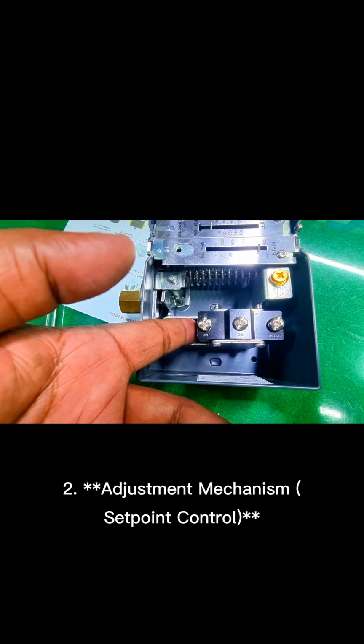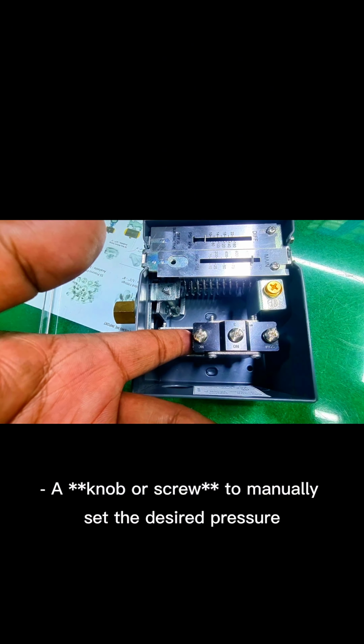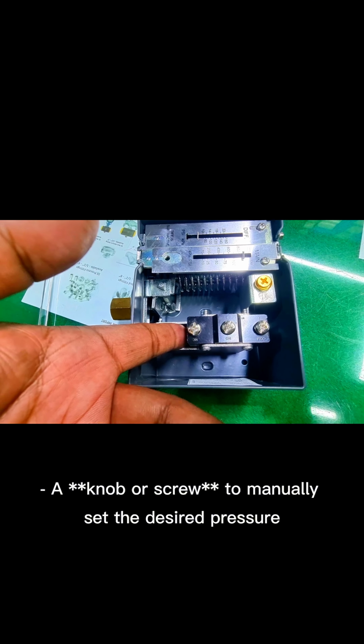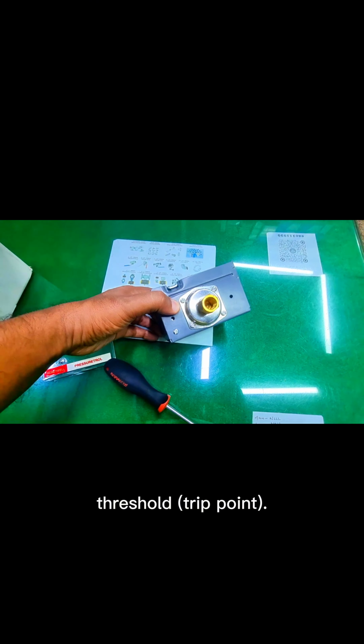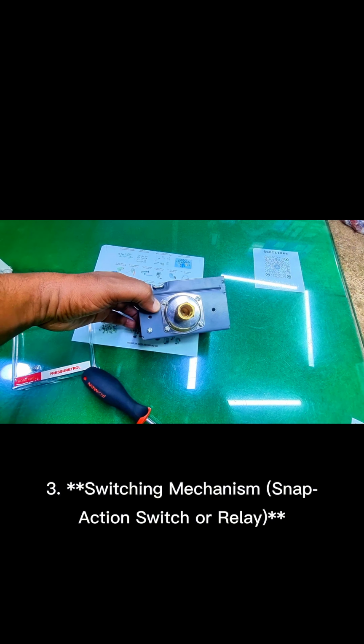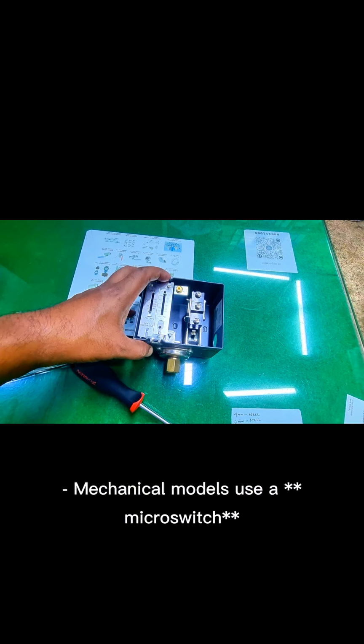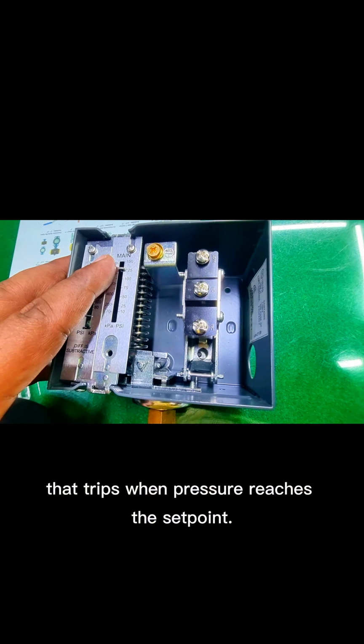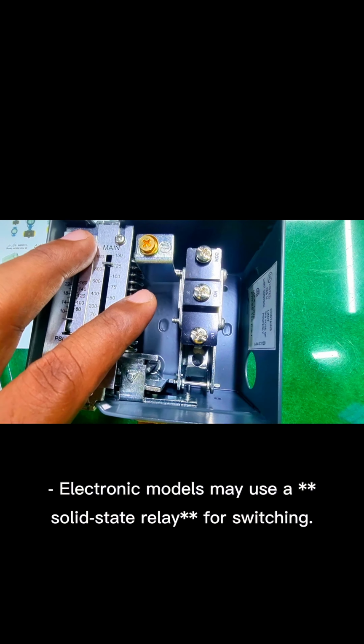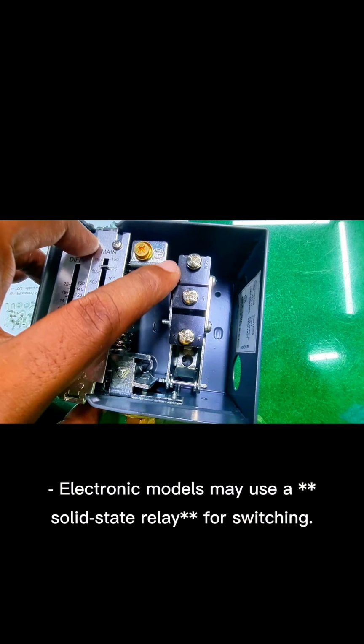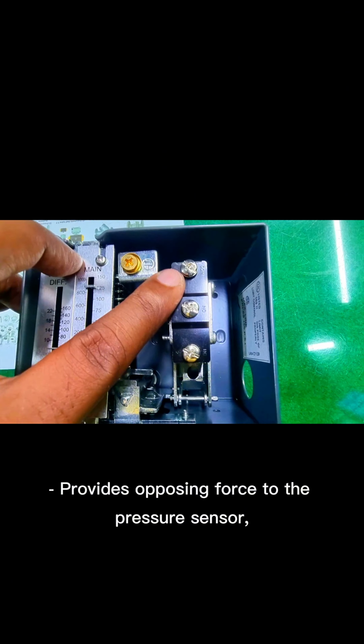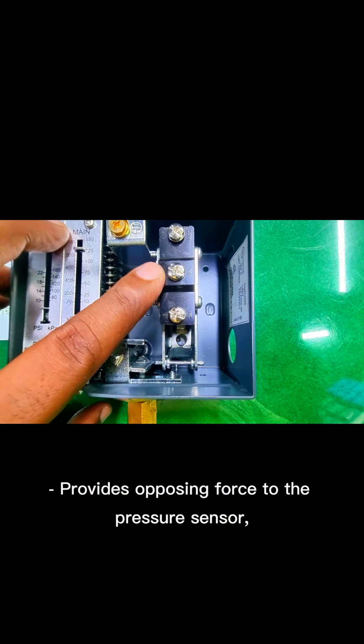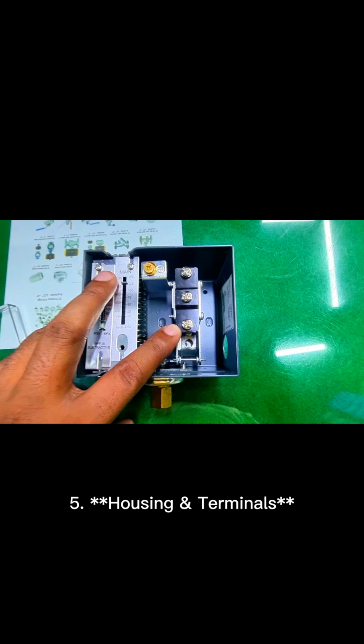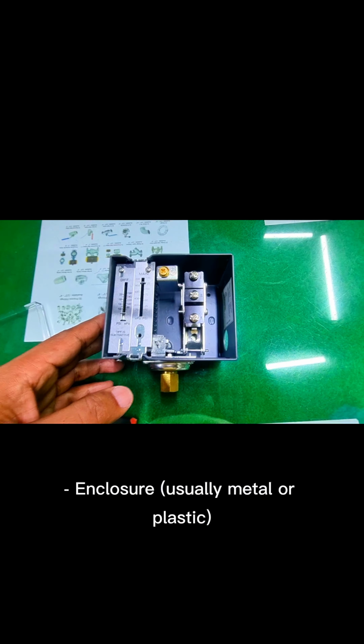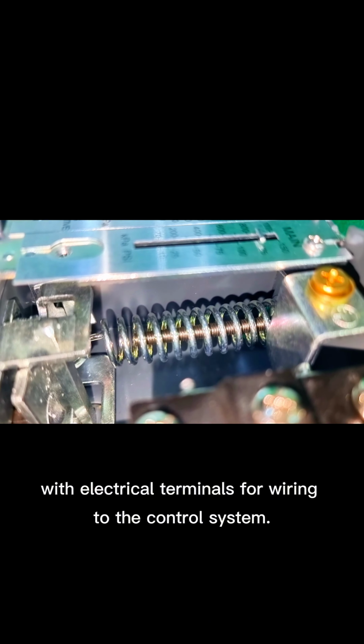The adjustment mechanism, set point control: the knob or screw to manually set the desired pressure, the threshold trip point. The switching mechanism, snap action switch or relay. Mechanical models use a microswitch that trips when pressure reaches the set point. Electronic models may use a solid-state relay for switching. The spring mechanism provides opposing force to the pressure sensor, determining when the switch activates. Housing and terminals: enclosure, usually metal or plastic, with electrical terminals for wiring to the control system.